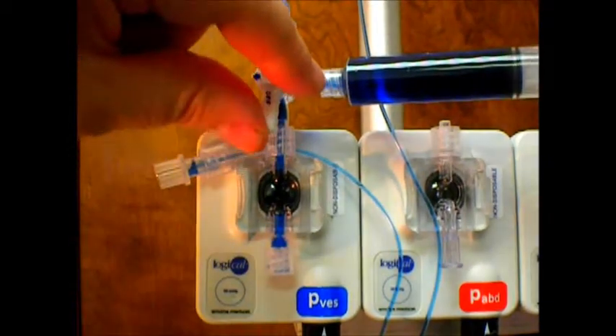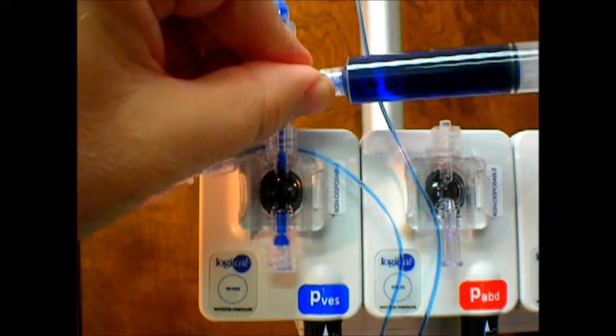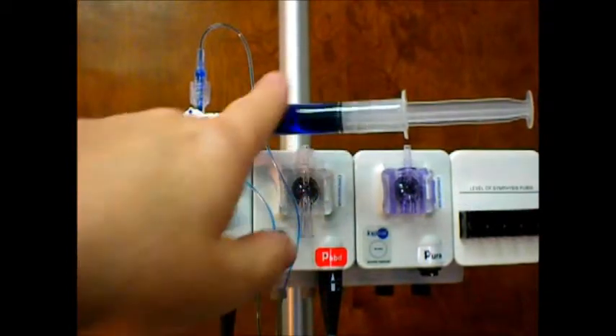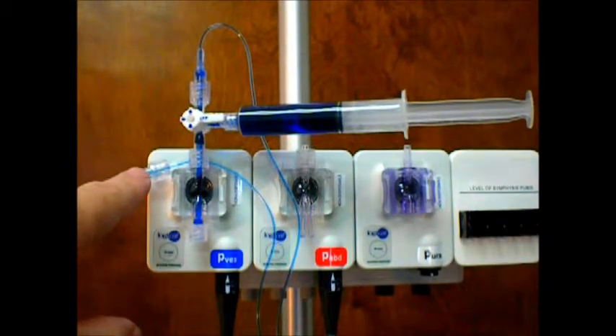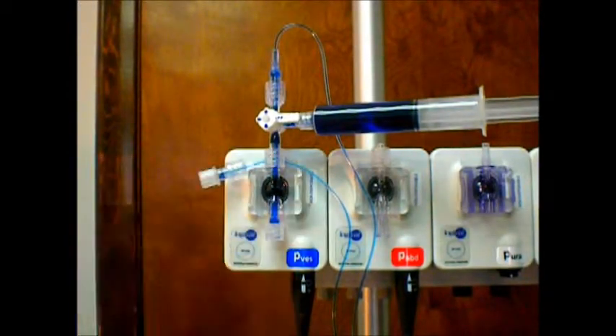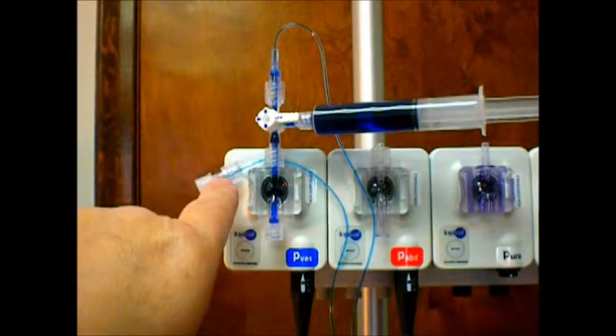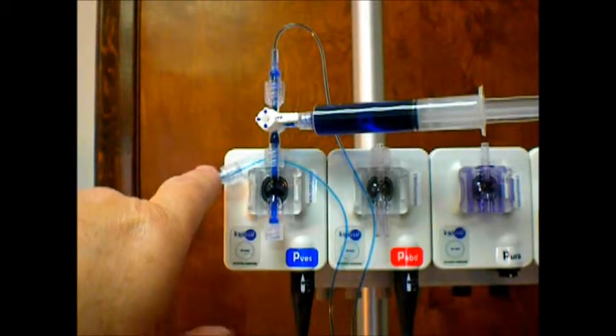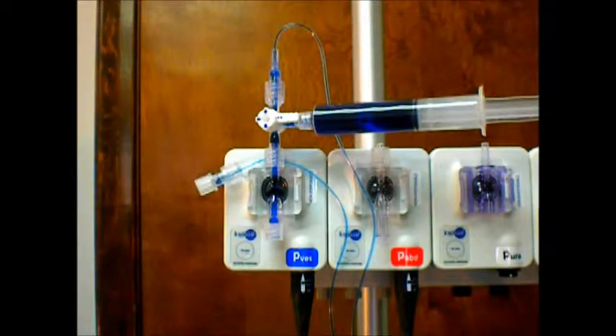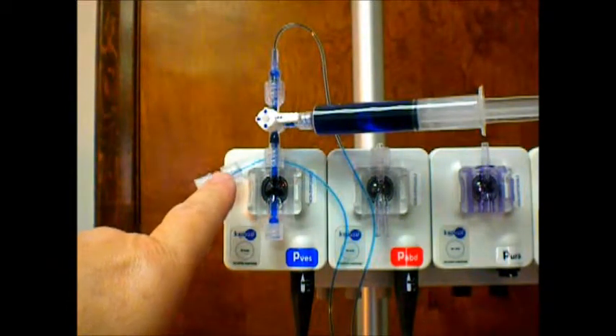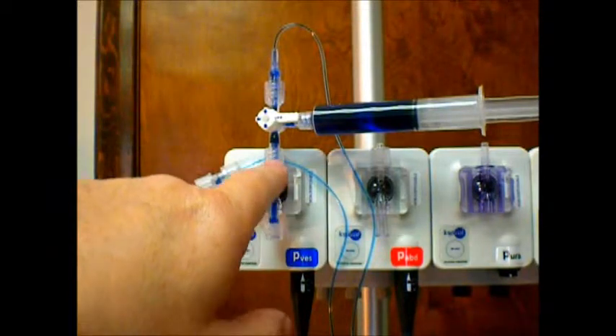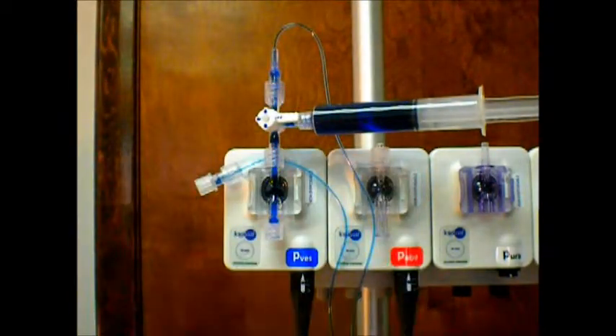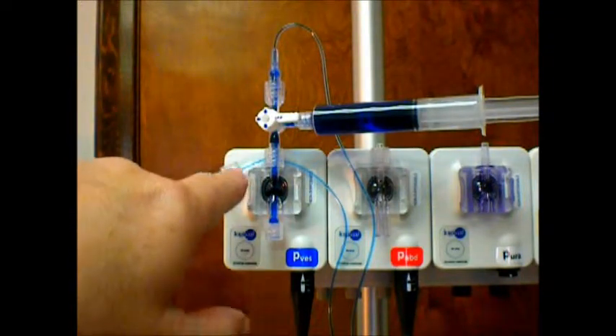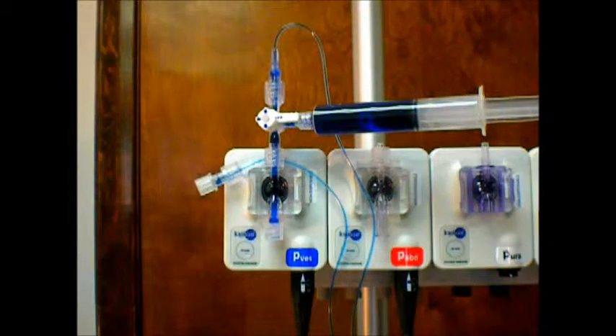This is the position that you want to have it in when you, let me take that back, because what we want to do is close off our stopcock to the syringe, so that now the pressure transducer is open all the way to the end of the pressure tubing. So now what we have is the transducer is open all the way through the pressure tubing to the end of the tubing. This is open to air. This is the position that you want everything at when you're ready to zero your transducer.